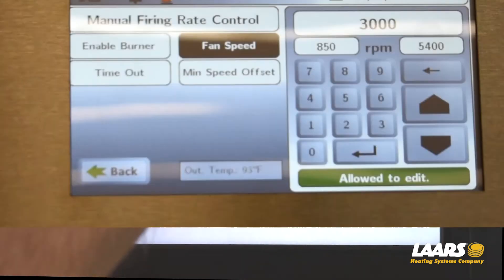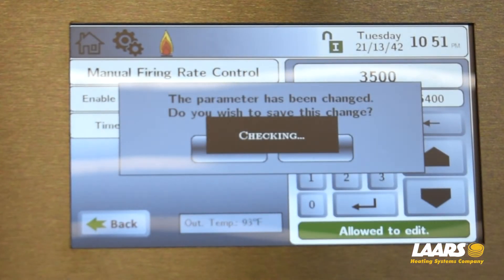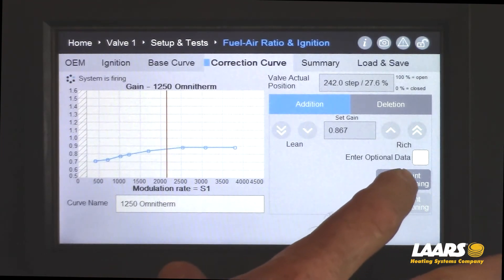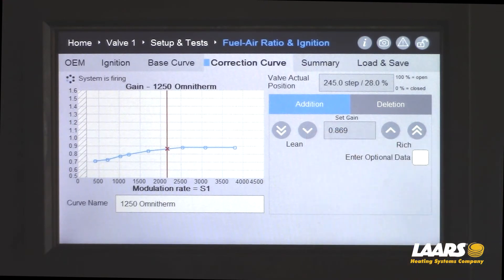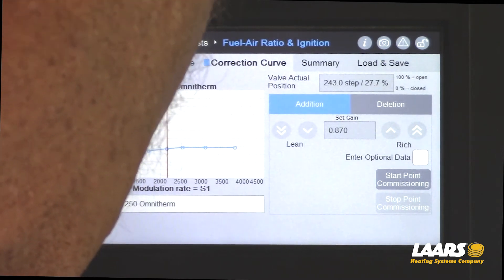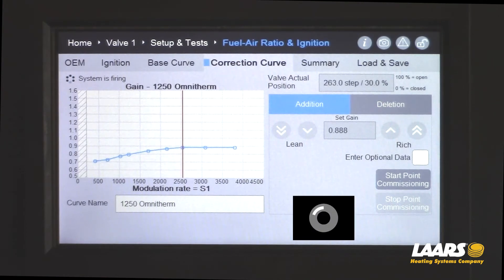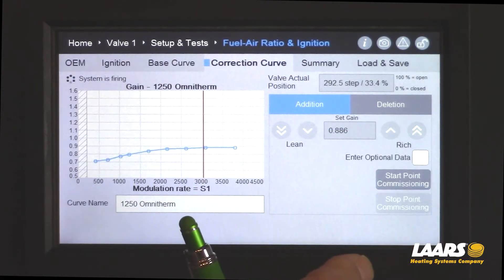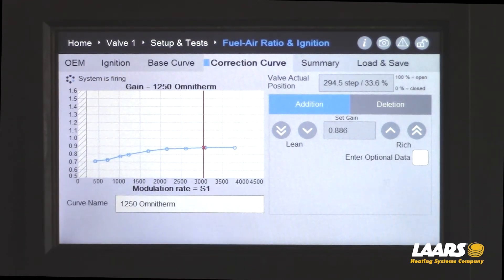Come back to your LAARS link and increase your fan speed again. Go to 3500 RPMs. Here's our next point — we're dialed in — and save that one as generic. Then go back to the link display and increase to 4000 RPMs. Wait for the indicator line to come up, check your analyzer, click start point commissioning, and save this as a generic as well. If a second point comes up, we will delete that.